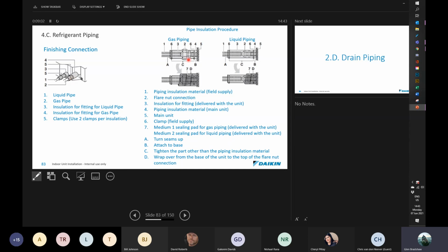I can't tell you how many times I sit in buildings and I look up at the ceiling around cassettes and things like that, and in one corner there's a telltale mark that the flare nut was never insulated, shown by the leak marks or the water marks on the ceiling. And often it happens, and you see in new buildings, brand new ceilings, in a short space of time, you can see the telltale marks of the insulation that has not been installed on the flare nuts. Please make sure that it's part of the installation, and if you can just get that in, it goes a long way to not having damaged ceilings.